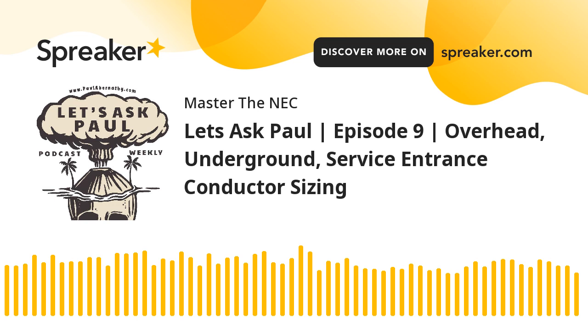All right, in this one, you're in Part 3, still in Article 230, but where we're going to go down is to 230.31. And you'll notice that it also says size and ampacity. And you have your general again, you have your minimum size, and we have grounded again. And again, it's going to be the same exact concepts, so we won't rehash this. It's going to tell you that the ungrounded service conductors shall have sufficient ampacity to carry the current for the load as calculated in accordance with Article 220. Same concept, mechanical strength, and so on.